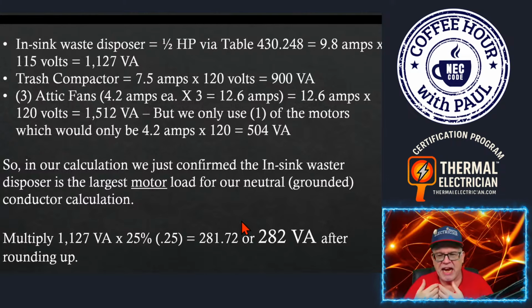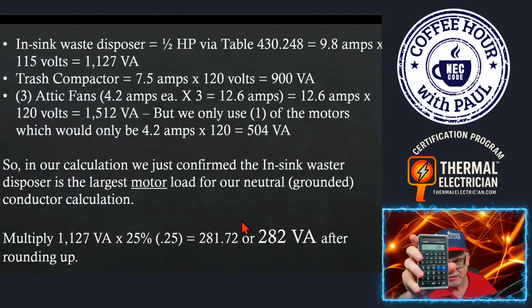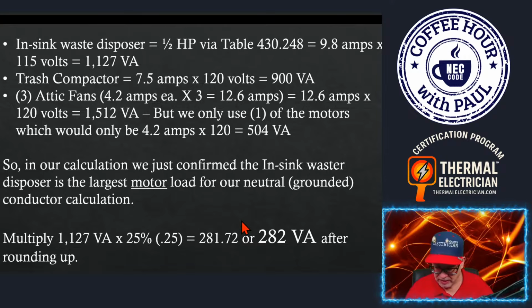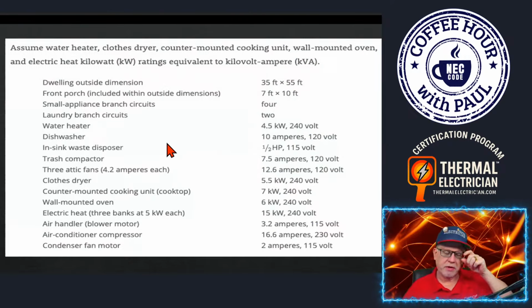In the scheme of life, how many amps does that bring? Well, you can see what it brings. If I take that 282 divided by 120, it's 2 amps. From a 240 volt service perspective, it's 282 divided by, well, no, we're just going to keep it that. That's the contribution it's going to be to any one of the legs, right? Whatever this neutral is using as the hot leg. So really, it's not going to change a whole lot in the real world. Okay, so we've covered this was everything, right?